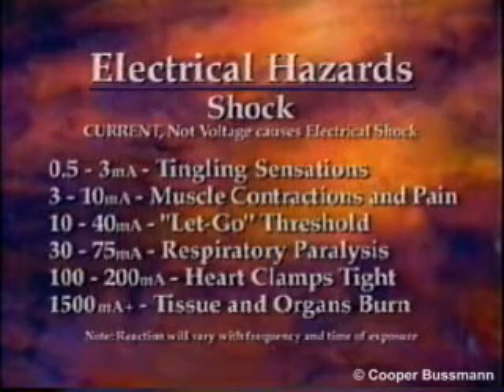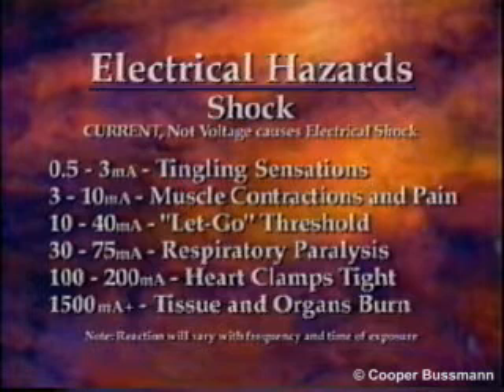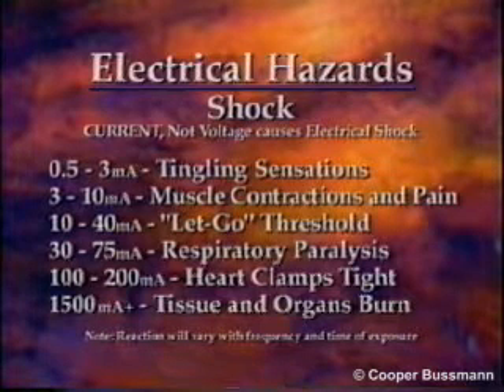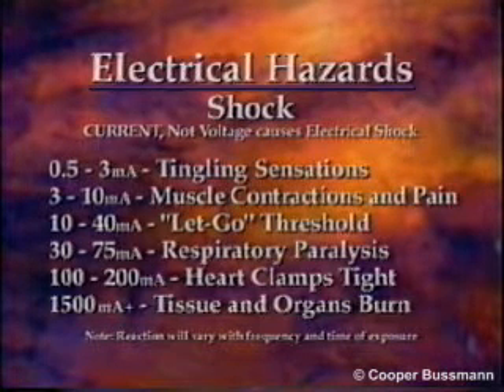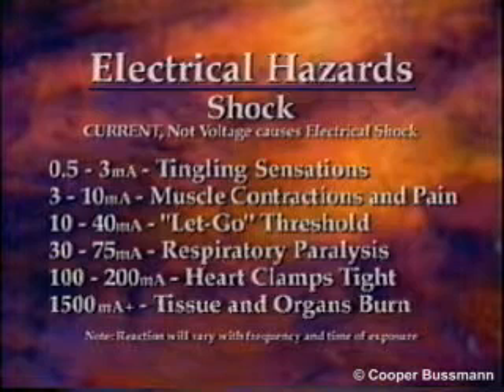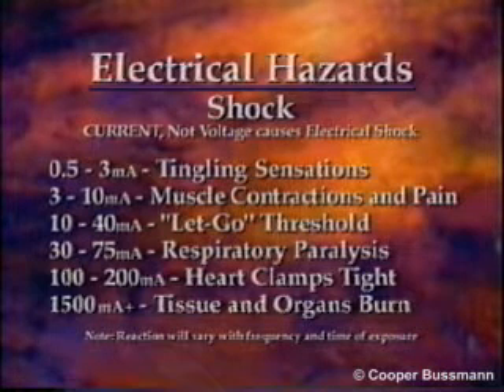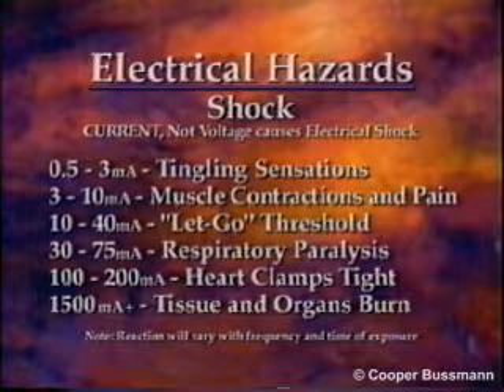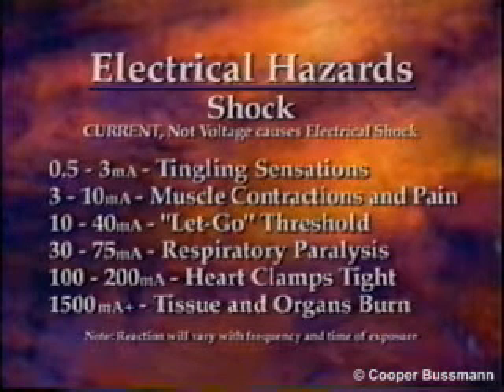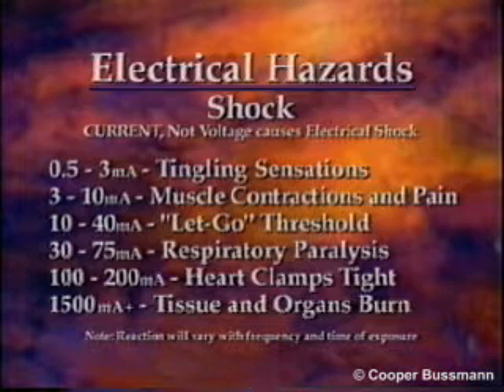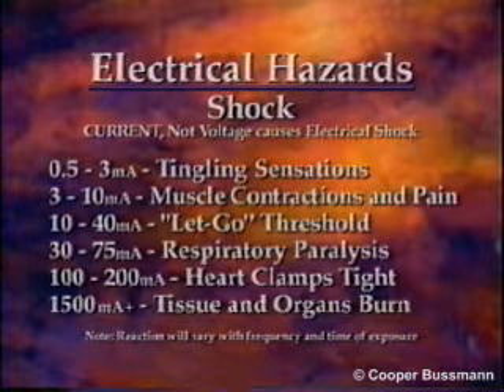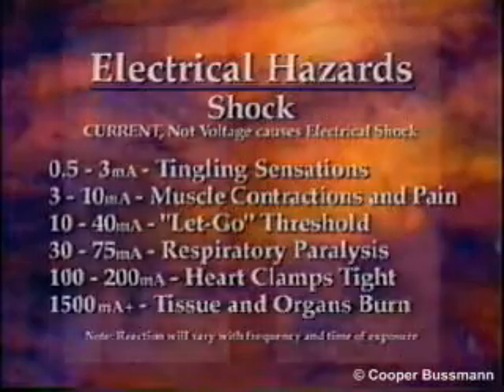This table shows how the body reacts to various levels of electrical current. At current levels as low as 15 milliamps, an individual's arm can lock up, making it impossible to let go of the conductor. This is sometimes referred to as the let-go threshold current. They may also be unable to speak or call out for help. The longer this continues, the greater the potential for serious injury.